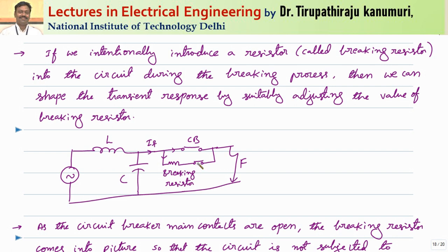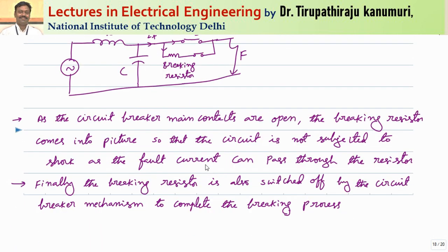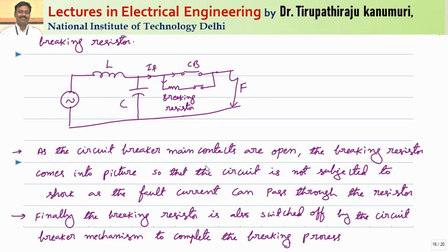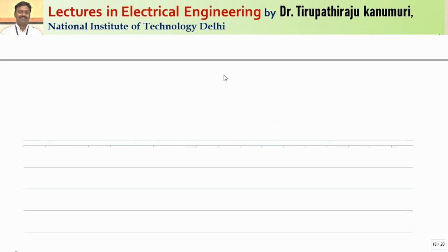Now we will derive how this arrangement improves or decreases the oscillations and what the ideal value of the resistor should be. Whenever the circuit breaker contacts are opening, the mechanism is designed so that the breaking resistor is automatically connected across the contacts. Once the circuit breaker is completely isolated, an auxiliary switch at the breaking resistor is also opened, completing the switching process. So, at the instant of opening the circuit breaker contacts, the breaking resistor comes into picture with the switch closed, allowing current to bypass. Once the contacts are completely open, the auxiliary switch contacts also open, completely isolating the fault.